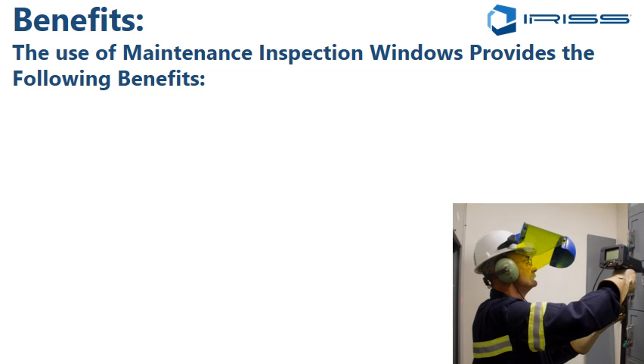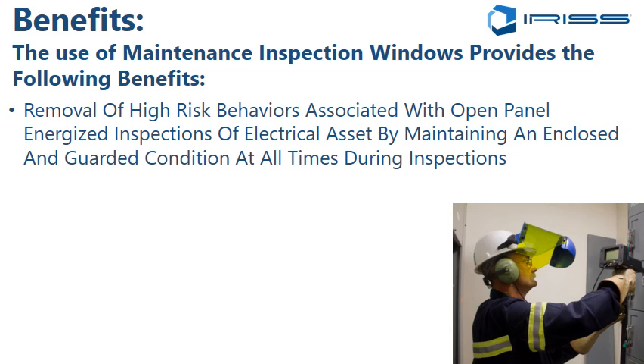So the benefits of utilizing a maintenance inspection window are that we remove the high-risk behaviors associated with open panel energized inspections of electrical assets by maintaining what we class as an enclosed and guarded condition at all times. Now we see grills being used a lot, and grills are guarded but they're not enclosed. The whole idea of an inspection window system is that we maintain the internal environment in a stable condition. If you open a grill, you're opening a large vent, and some of these grills are 6 inches by 6 inches, I've seen them, and those can actually enable an arc flash event to occur because we're not maintaining that enclosed condition. So make sure you have an enclosed and guarded condition at all times.